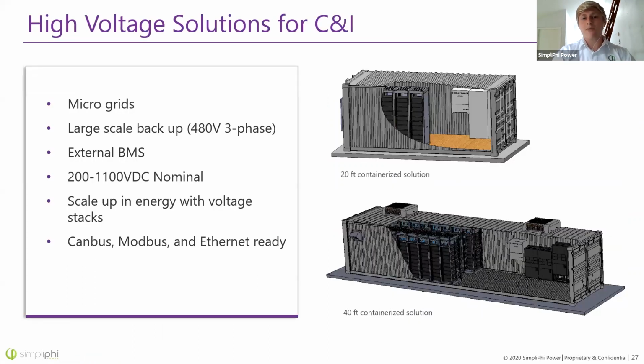Moving to our high voltage solutions, this is more for commercial and industrial solutions, such as microgrids even. It's able to provide 3-phase power, reaching up to 1100 volts DC nominal. This is a bit different than our other batteries because the BMS is no longer internal, it's actually an external BMS, allowing it to scale to a higher voltage. It's also CAN bus, Modbus, and Ethernet ready for communications.